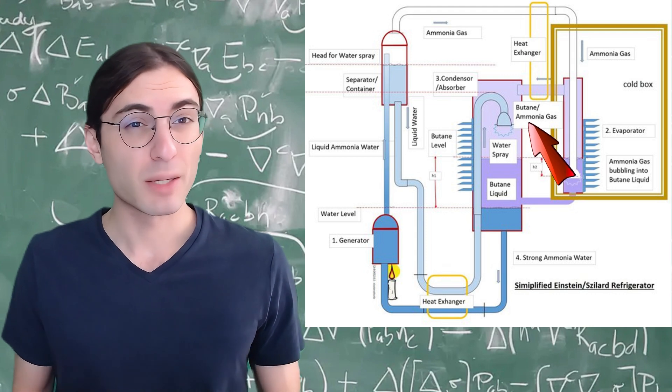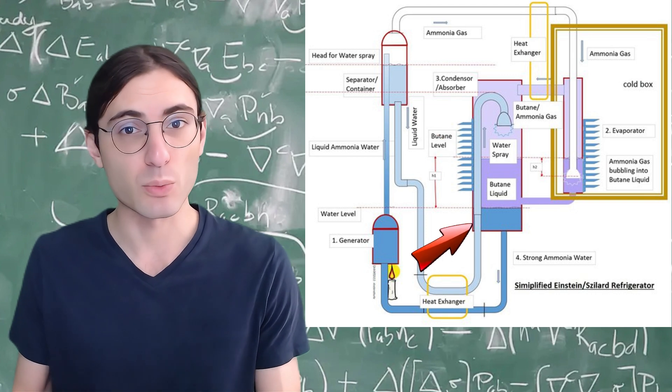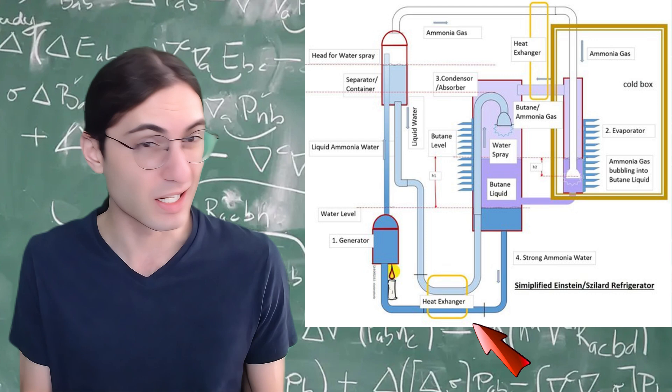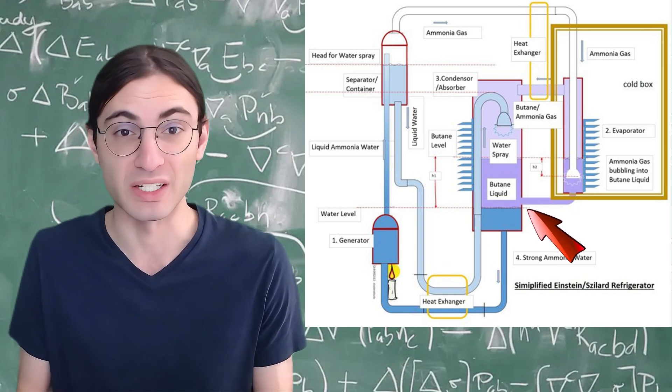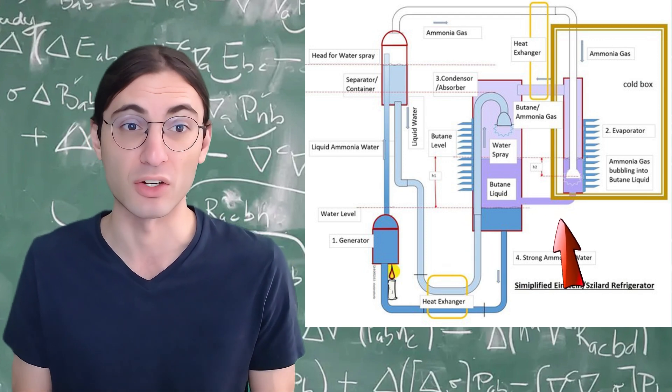Next, that butane-ammonia mixed gas feeds into a condenser where some pre-cooled, ammonia-poor water is sprayed. This water then absorbs the gaseous ammonia, which condenses and sinks to the bottom, feeding back to the heating chamber. The butane, now being the majority again, having high partial pressure, recondenses, releasing heat. This heat is then dumped to the environment, and the liquid butane is then fed back to the evaporating chamber.